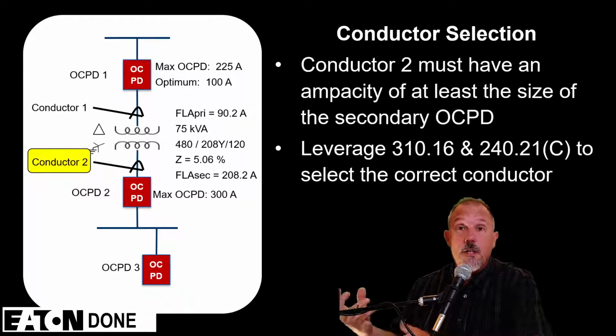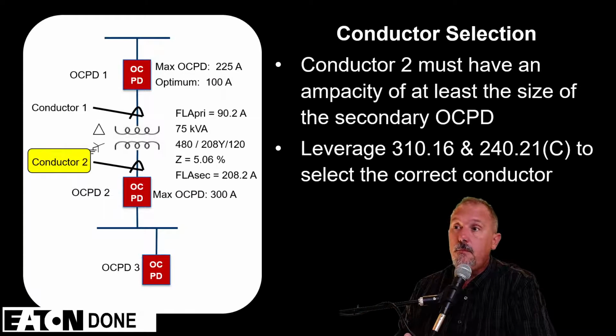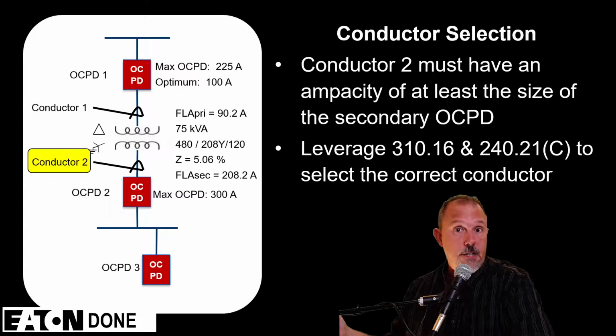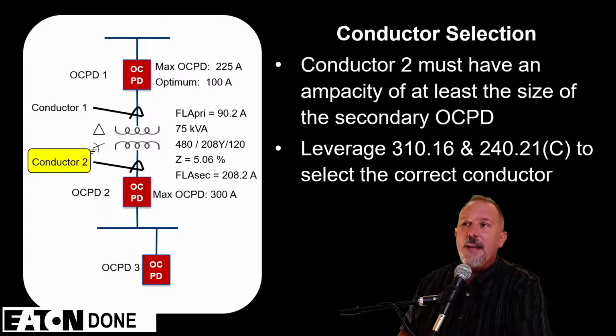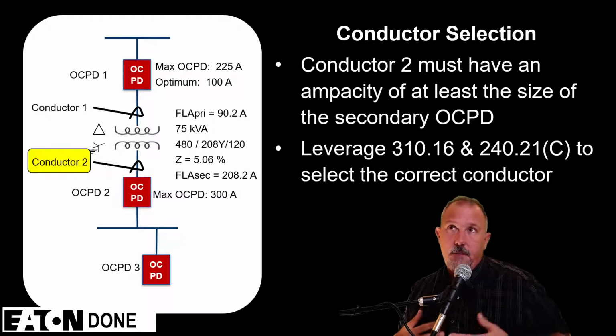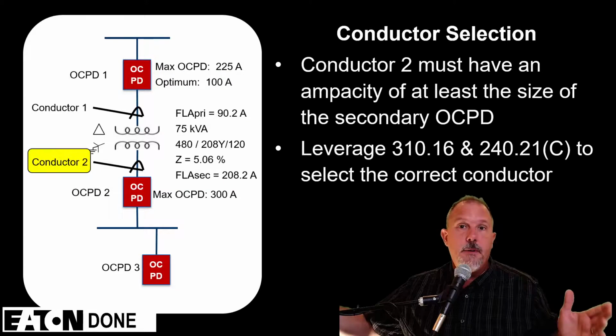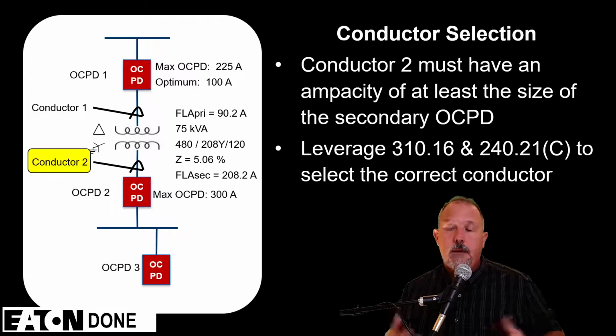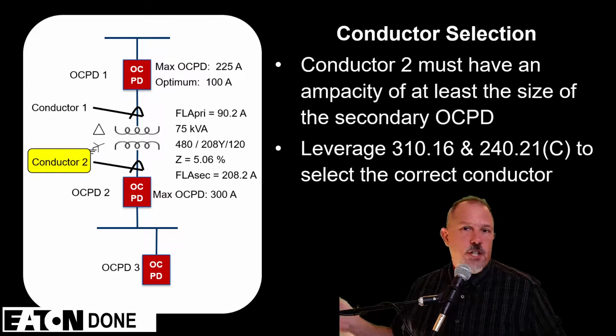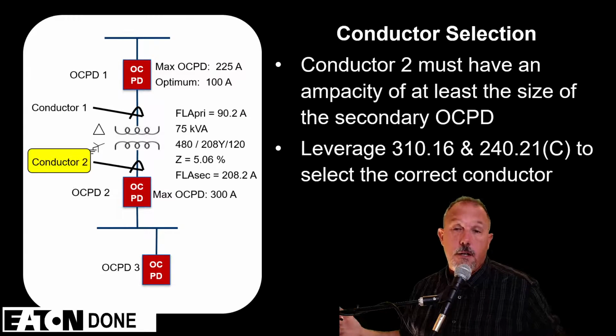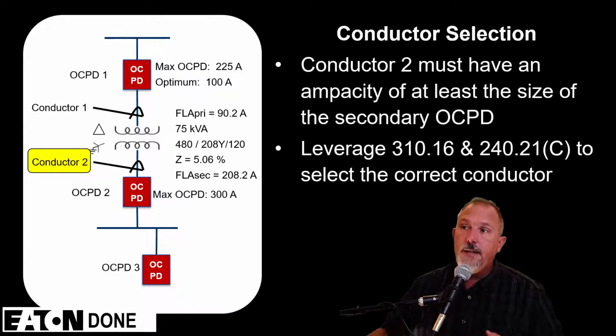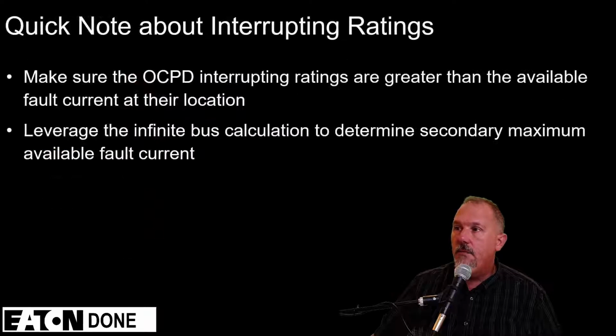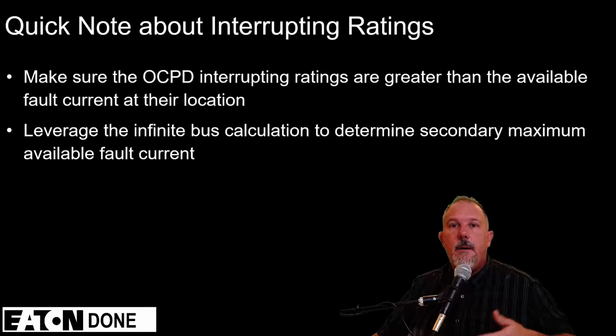So I can put a larger conductor than what I need, maybe for future expansion if I want to. But in my experience, that panel board's typically been right next to the transformer in many cases. So if I'm going to change that panel board out, I'm just going to pull a new conductor in the conduit. Even if I have to change the conduit, it's not a big deal. So in any case, I've gone through the primary and secondary breakers, primary and secondary conductors, piece of cake.